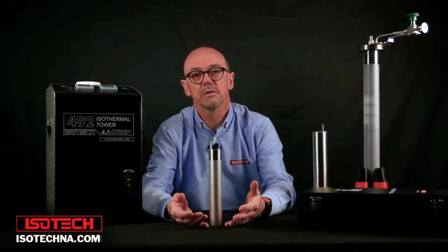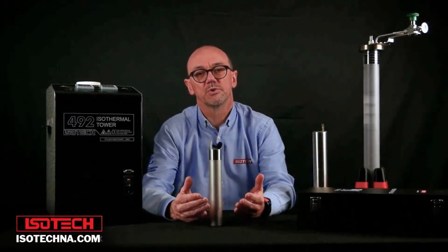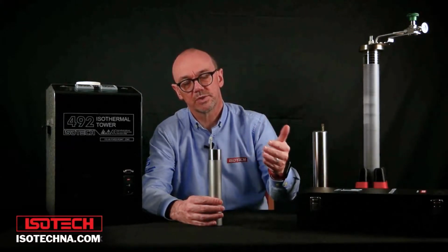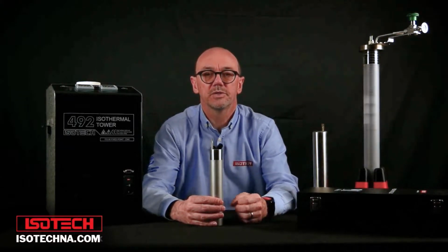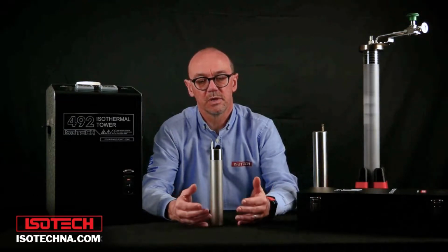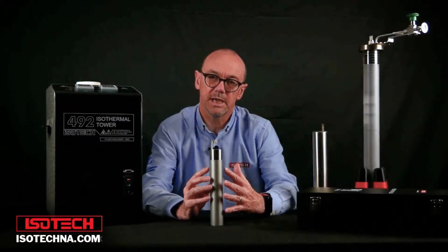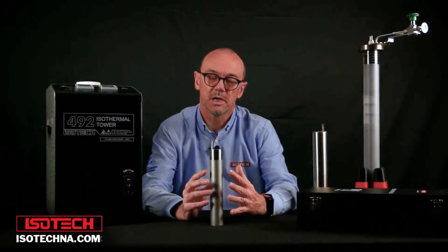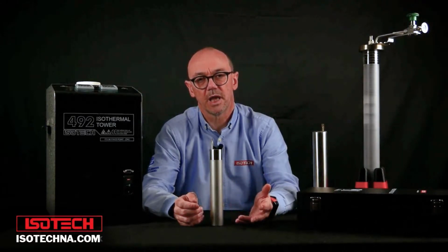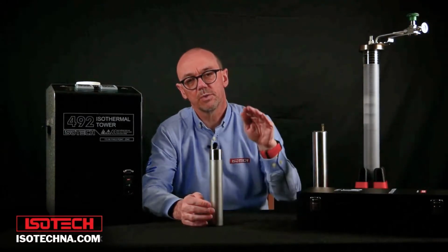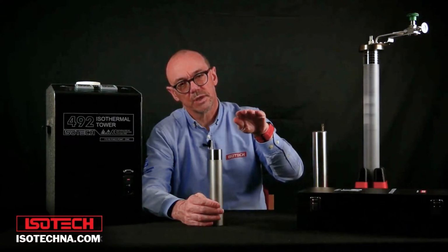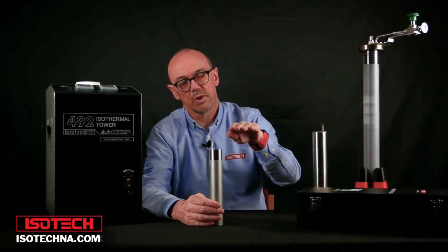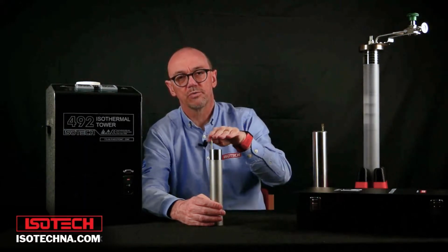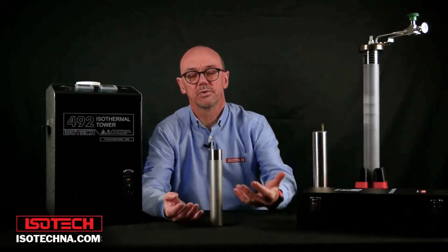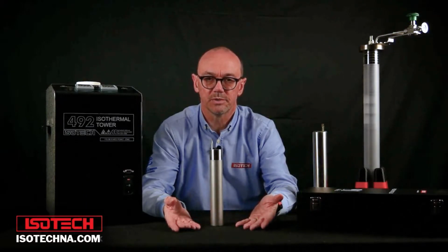But to use the cell, I need to put it into a furnace or some sort of calibration equipment to raise the temperature. So tin melts at about 232 degrees. So I'll raise the temperature to a little above that until the solid tin melts, and then I'll lower the temperature of the calibration equipment so the liquid tin slowly freezes. As it goes through the phase transition from a liquid to a solid, we get a known and constant temperature, and that's used as the point to calibrate our thermometers.